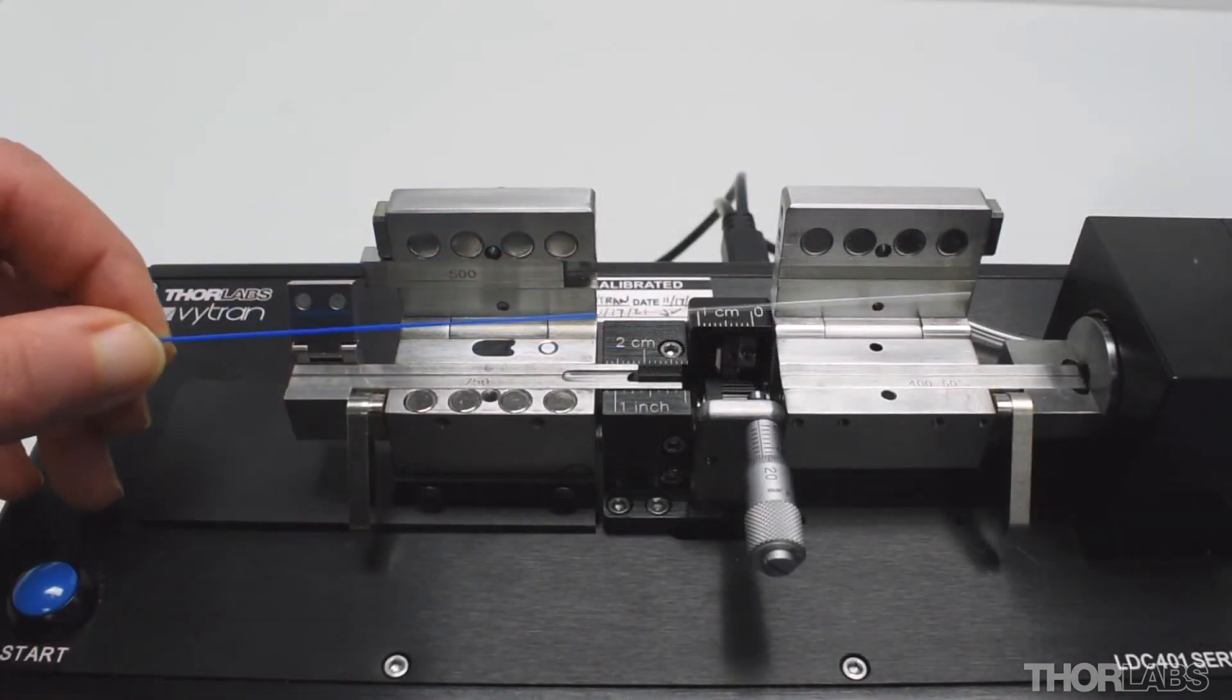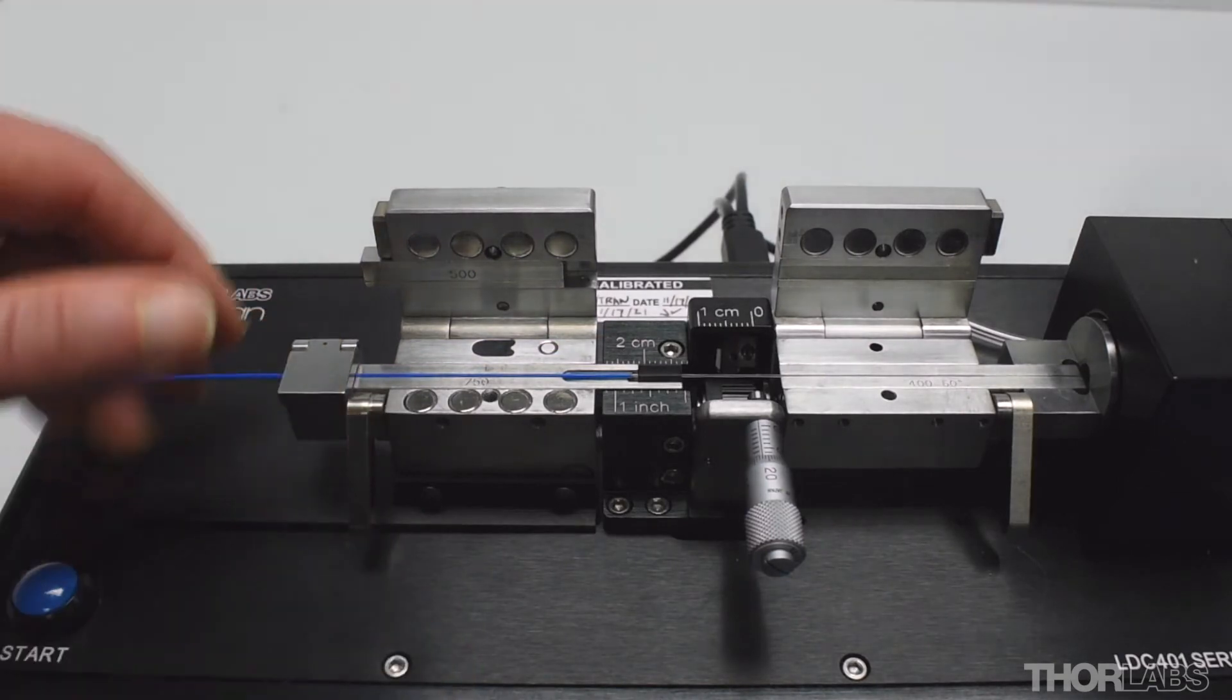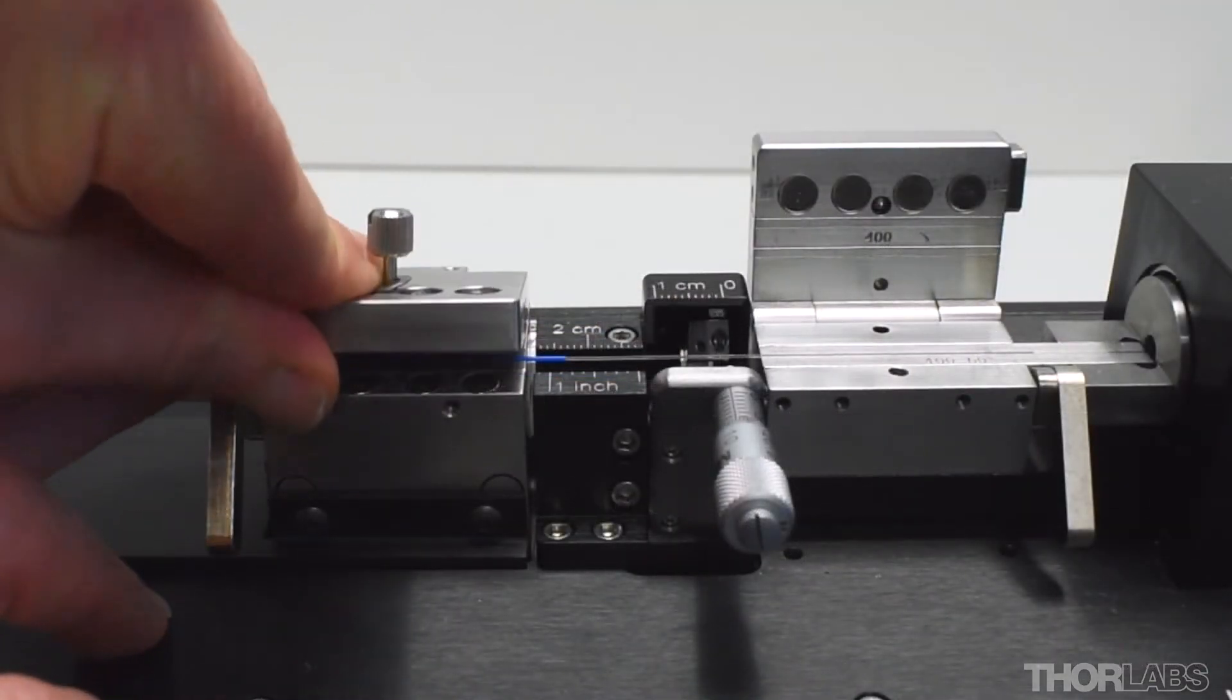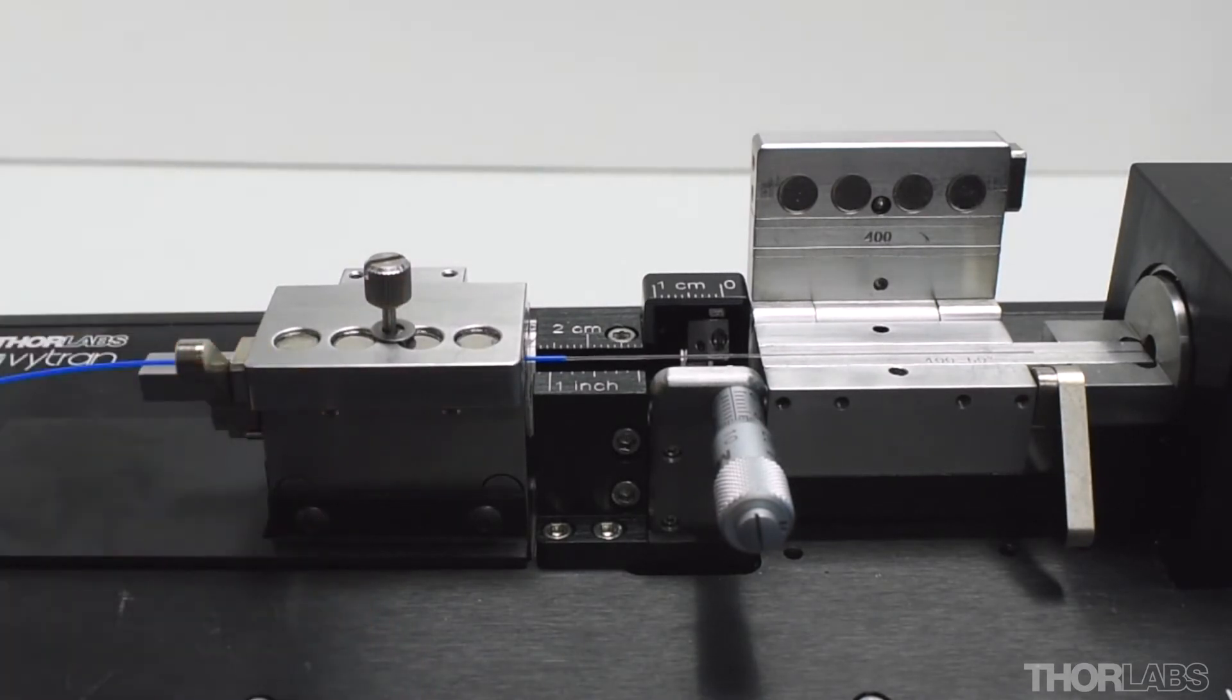If a transfer insert is being used in the left block, close the transfer clamp lid first, then lower the left lid and gently lift the cam lever to fully close it.